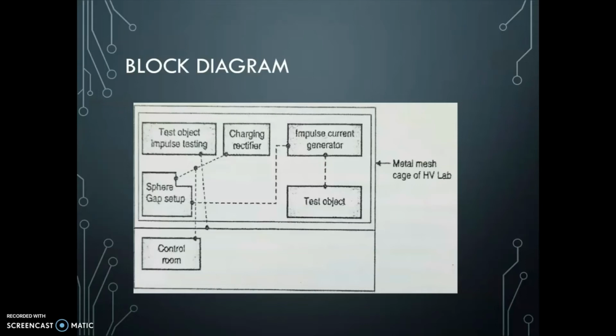To minimize the inductance of the grounding system, copper strips are used instead of a ground conductor. The earthing grid provided below the HV laboratory floor must have close spacing between the copper strips. The earthing system should be symmetrical in geometry. This one is a point of concern. It should be arranged such that loop current flow and loop voltage drops should not take place. The control cables and signal cables should be carried through metal conduit to avoid any kind of interference of mutual inductance effect.